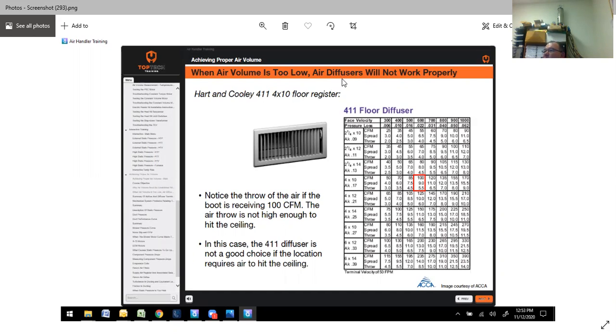Also, the air volume level will affect how the duct system delivers air to the individual zones. When air volume is too low, air diffusers will not work properly. Notice the throw of the air. If the boot is receiving 100 CFM, the air throw is not high enough to actually hit the ceiling. In this case, the 411 is not a good choice. This is using the Hart and Cooley chart here. It won't give you enough throw to hit the ceiling.